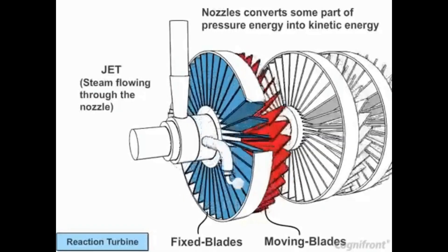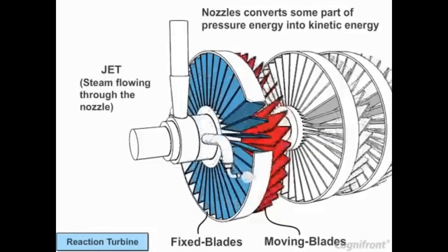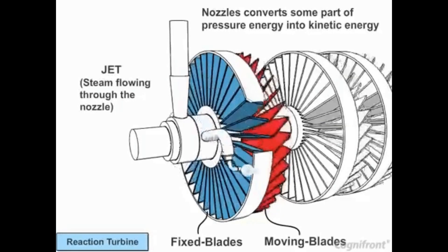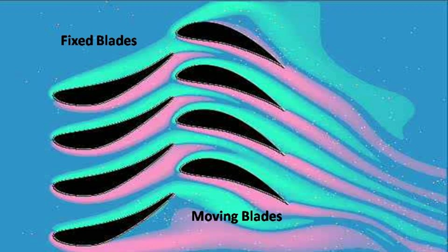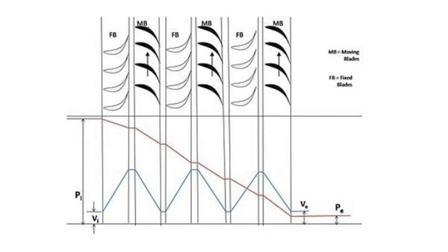A reaction turbine has rows of fixed blades alternating with rows of moving blades. The steam expands first in the fixed blades where it gains some velocity as pressure drops — this can be called the nozzle effect. Then the steam enters the moving blades where its direction of flow changes, thus producing an impulse force on the moving blades. In addition, the steam upon passing through the moving blades again expands and further drops in pressure, giving a reaction force to the blades.